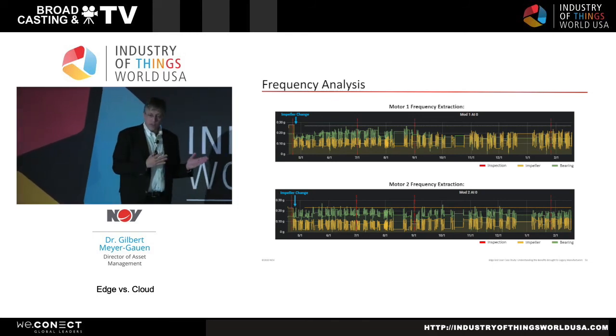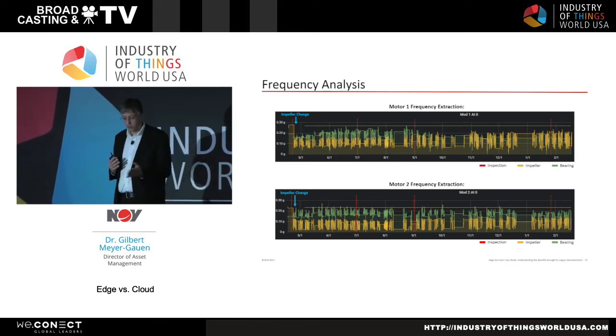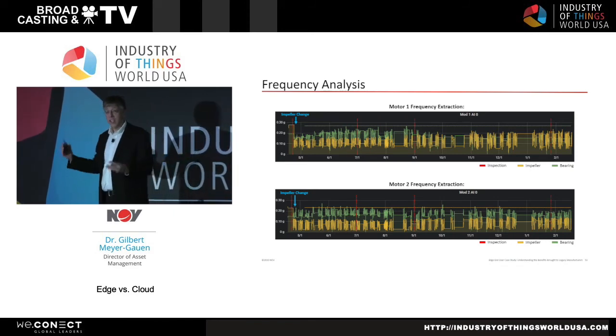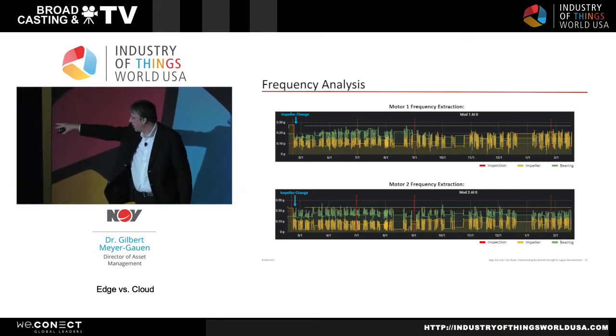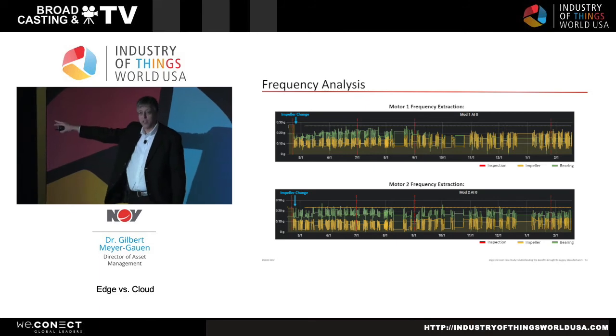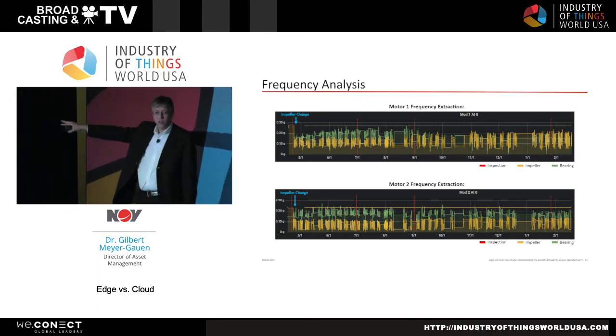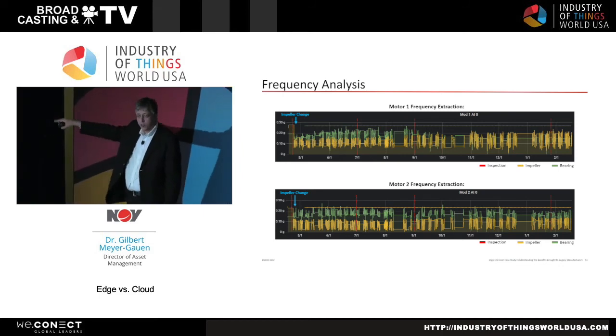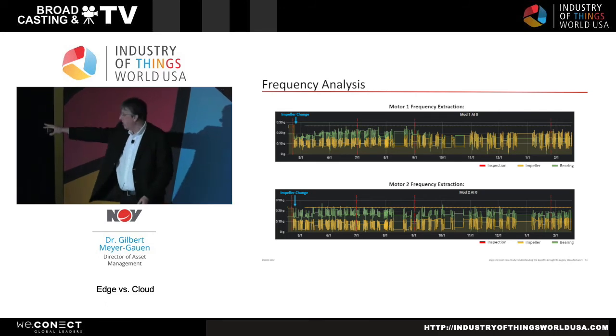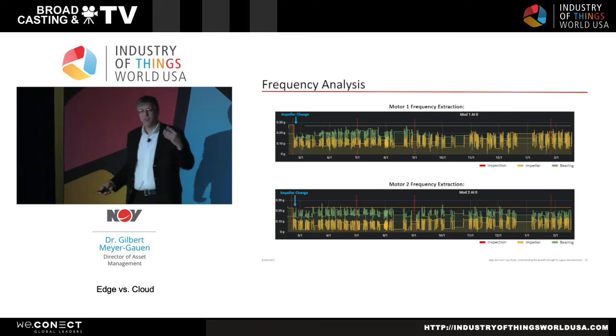And because it's the first time we did it, we still do visual analysis to really make sure that what we are measuring represents the actual case. And this is what I will show you. These red dotted lines are the next 4 slides from left to right. So obviously, the first slide will show you a picture of these impellers before we changed it. And then the next line will show it after 370 hours, 720, and I think these are from this year, just fresh off the press, after 1,250 hours or so.